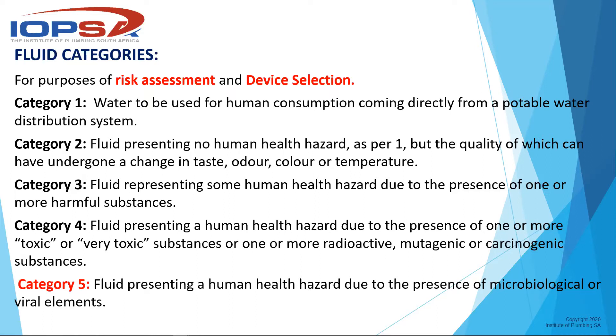Category three is fluid presenting some human health hazard due to the presence of one or more harmful substances. Category four is fluid presenting a health hazard due to the presence of toxic or very toxic substances, like radioactive, mutagenic, or carcinogenic substances - most medical installations fall here. Category five is the worst, where fluid presents a human health hazard due to microbiological or viral elements.